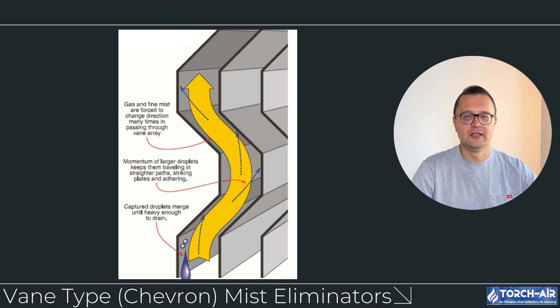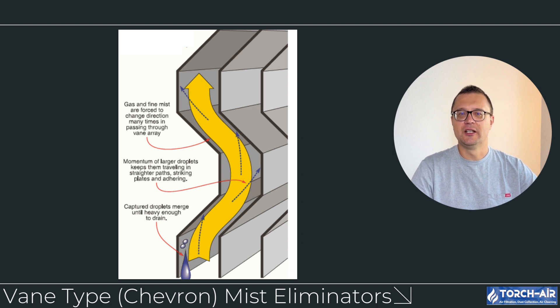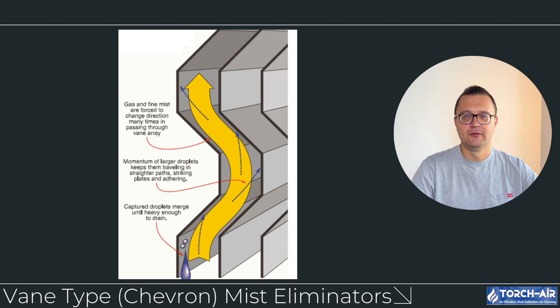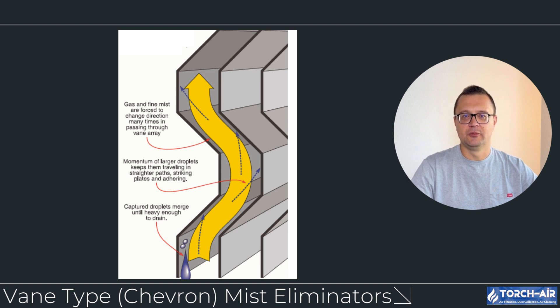The second type is vane-type, or chevron, mist eliminators. These use a series of curved or angled plates to capture droplets. As the gas stream passes through the vane structure, droplets are forced to change direction, causing them to collide with the plates and coalesce. Best for large to medium droplet sizes, these systems are effective for high-flow gas streams and are relatively resistant to clogging since there are no small gaps like in mesh pads. However, they are not as effective for capturing very fine mist, but are great for applications with high liquid load.